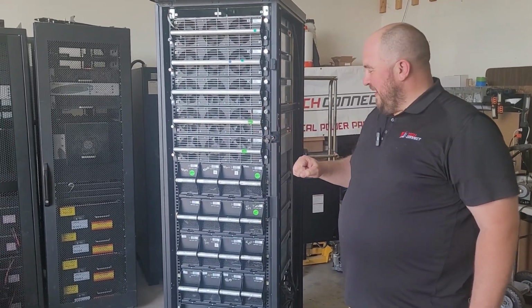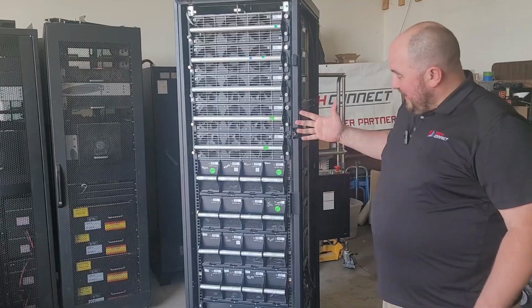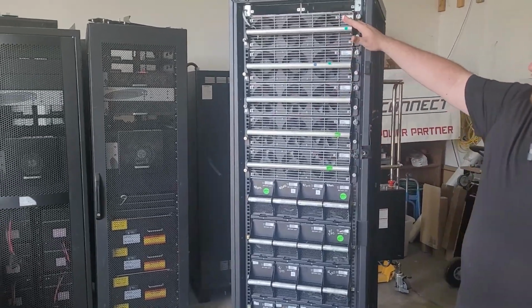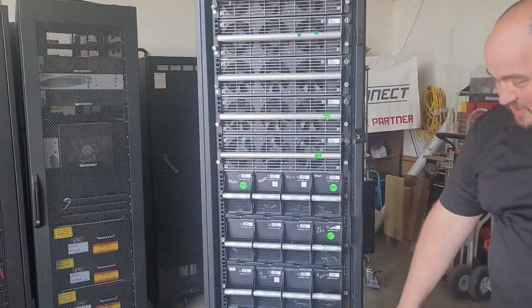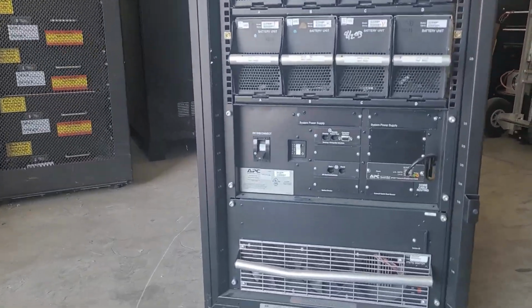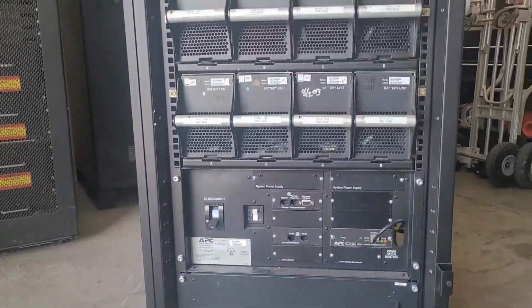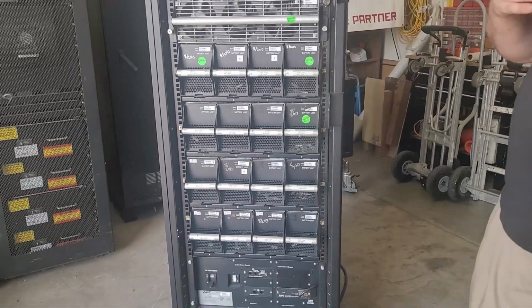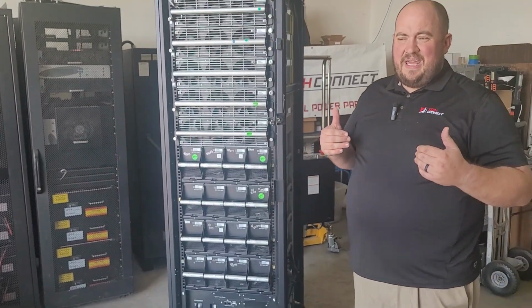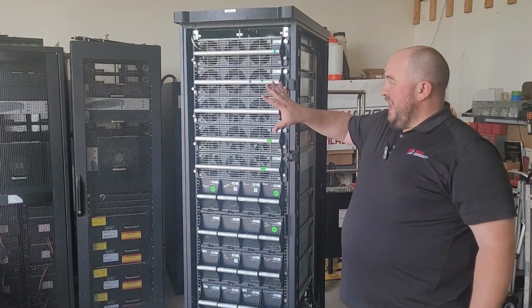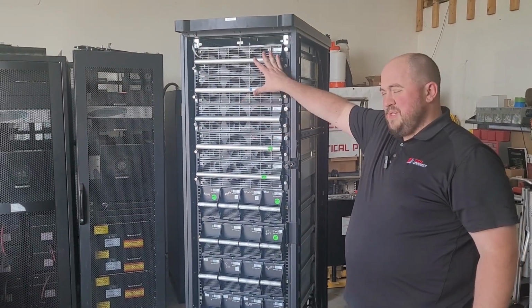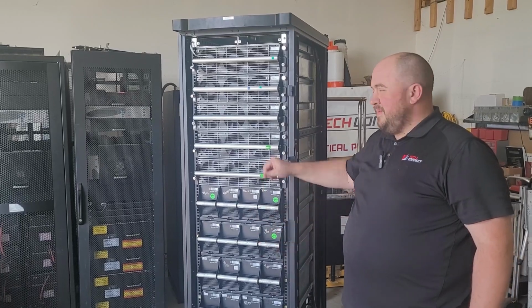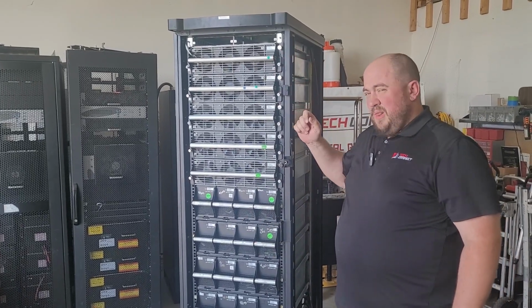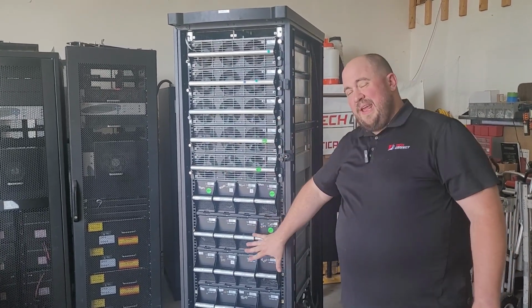So this is a three-phase unit. It's 40 kVA, 4 modules plus 1 redundant. It's got a static switch down at the bottom, controls, and then battery modules in between. So they made these in a 40 and 80 kVA module, meaning that they could take 4 here plus 1, or they could take 10. So plus 2, which would allow for 80 kVA. You would not have batteries in that one.